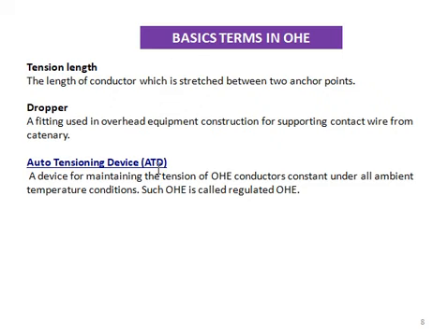Next, auto tensioning device, ATD, we have discussed in the last video also. It is a device for maintaining the tension in the OHE conductors. Here conductors means catenary as well as contact wire. So it will maintain the tension at all the temperature condition. And the OHE which is having auto tensioning device is called regulated OHE.